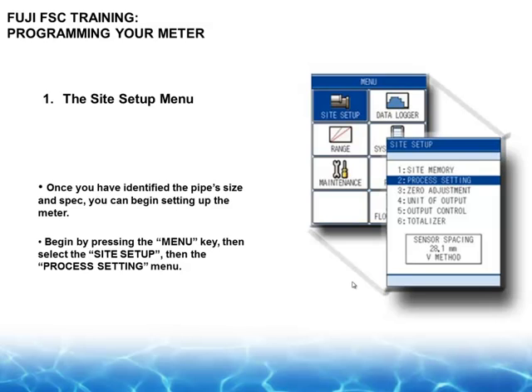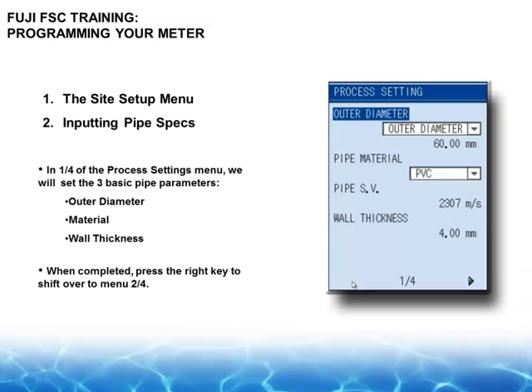So to set up for an application, step one, we go to the site setup. To get there, we basically press the menu key, then select site setup, and then we go to the process setting menu. Once we're inside, you'll see a number of pages, and they'll go from page 1 to 4. In the process setting menu, we will set the 3 basic pipe parameters. The one on the top there, although this is set in metric, of course we can program it in English. You have a drop-down menu. You can do pipe OD and so on.